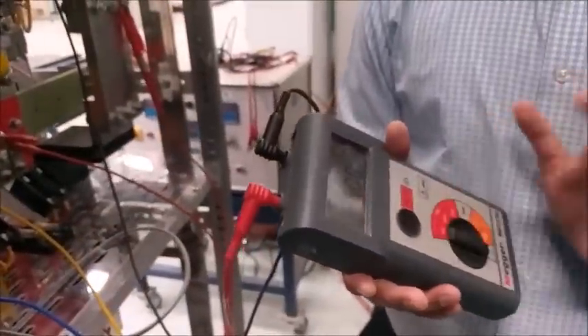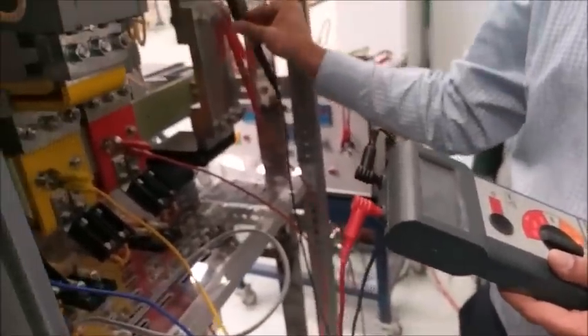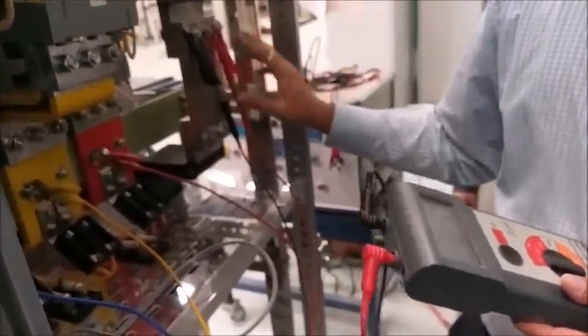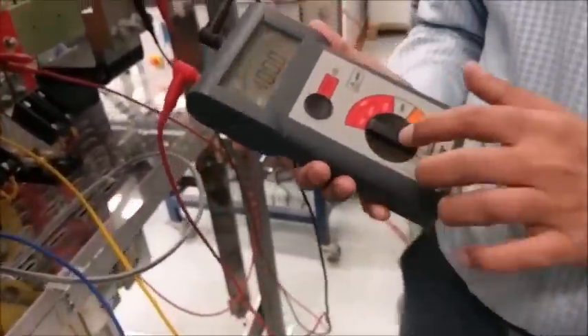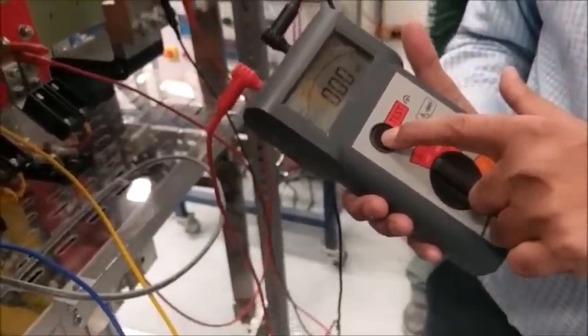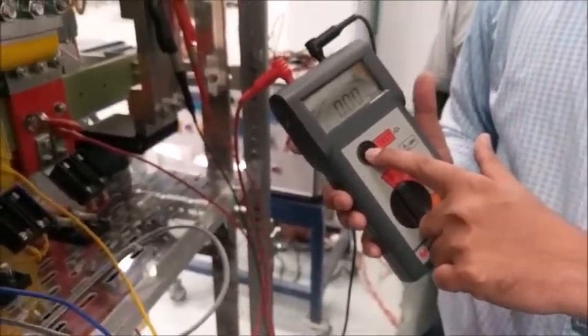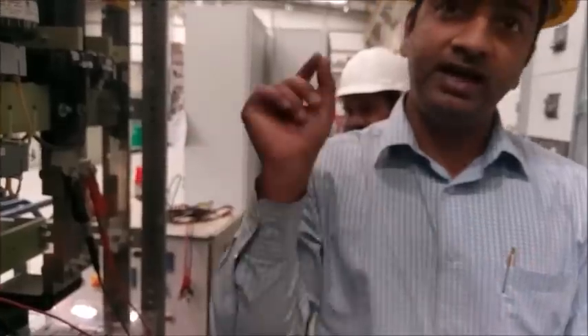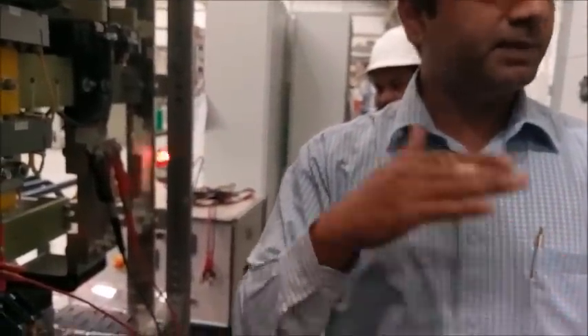Now, how do you test that this is working fine? If I connect this connection to here again, it is now a short. Insulation fail. It should show zero, no insulation. It's fail. Now it's working. So whenever in the total panel there is an insulation failure in any case, between any phase with respect to neutral or phase to phase, this will detect it at any case.